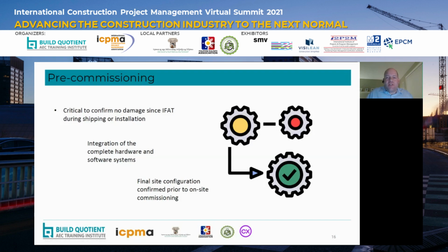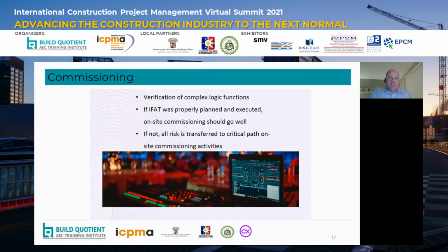A lot of the pre-commissioning checks are going to focus on the wiring, the cabling, the things that didn't exist during factory acceptance testing. So where you can find errors is in cables that are pulled, any terminations that are incorrect, and that'll be the focus of pre-commissioning, is to make sure that the cubicles can communicate with the end devices, that everything is essentially installed correctly in its final site configuration before we move to the next phase of the project, where we focus on then functionality of the system. And that takes place during commissioning.